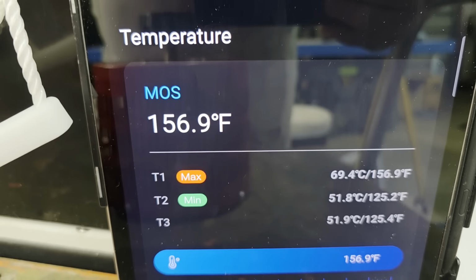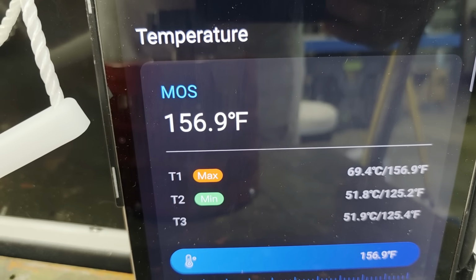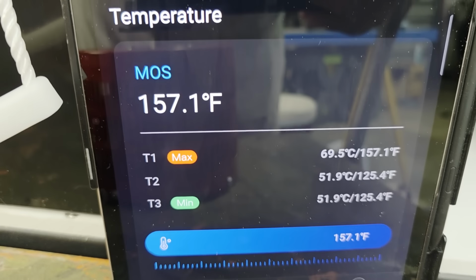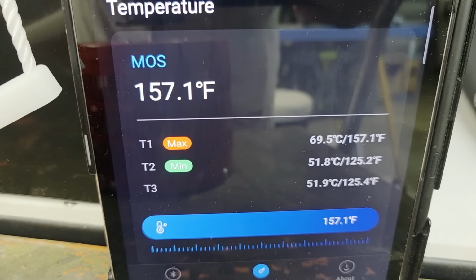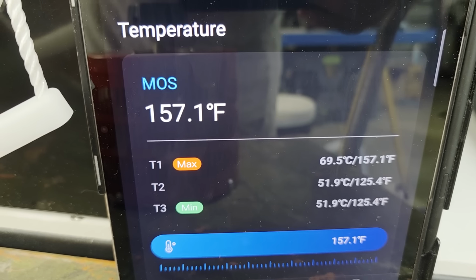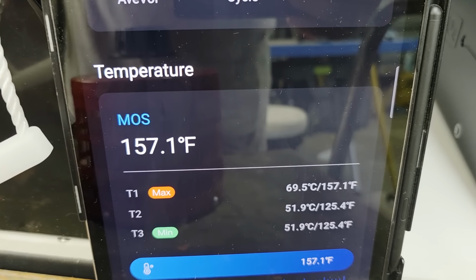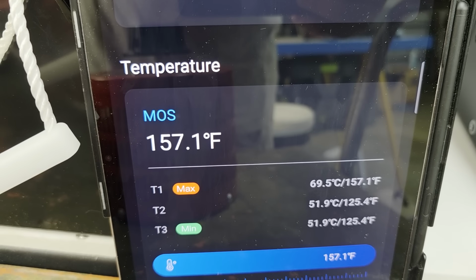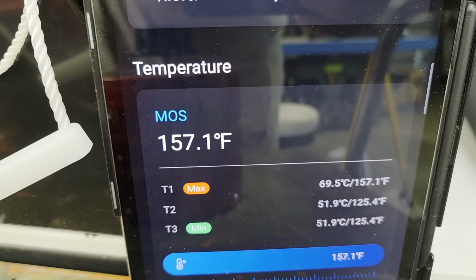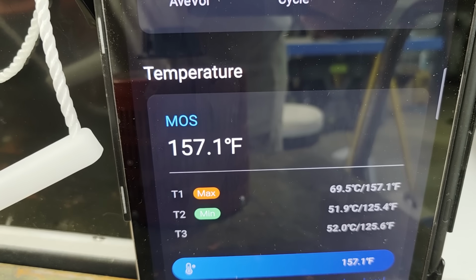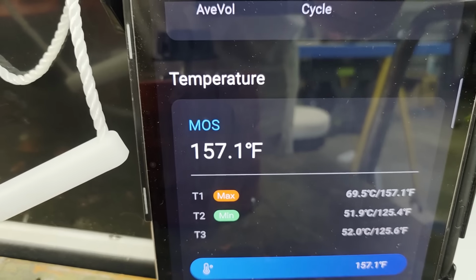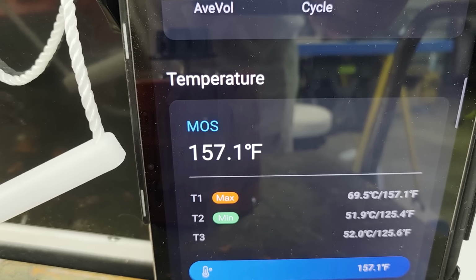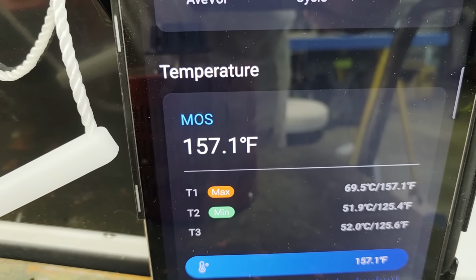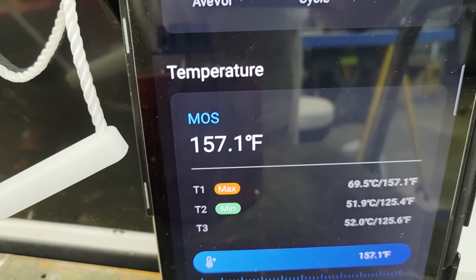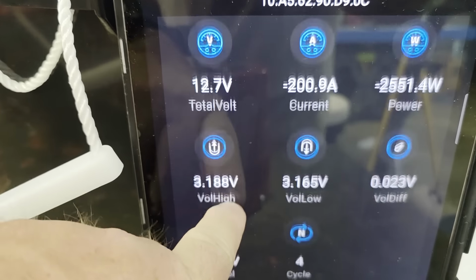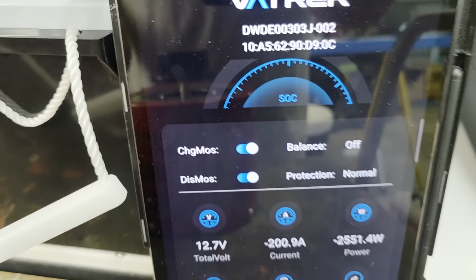156 degrees Fahrenheit on the MOSFET, 125 on the cells. Cell temperatures probably more than you want to see, but it's not unusual necessarily. I think you look at cell ratings from cell manufacturers and they were approaching those limits, but it did hit the rated discharge capacity that it says, and it did it from 100% to 20%. And it would make it to 0, I'm pretty sure.